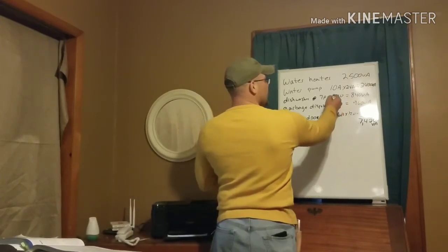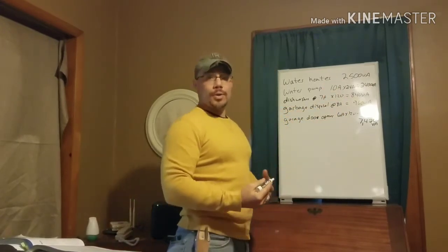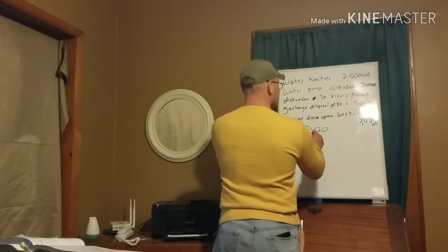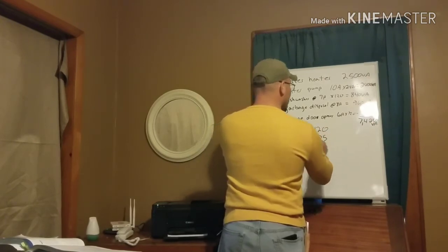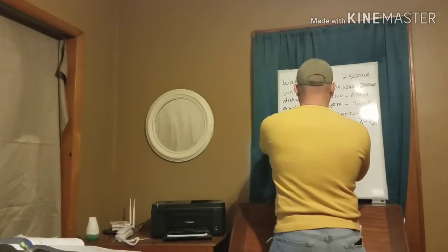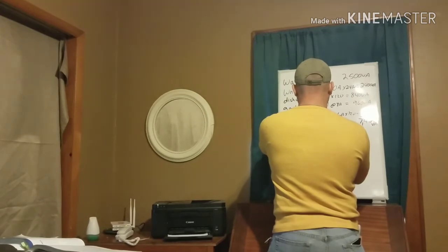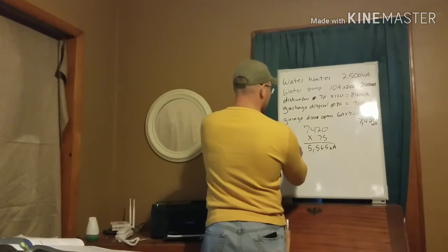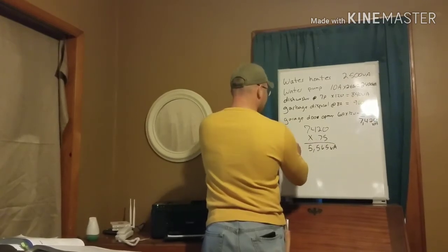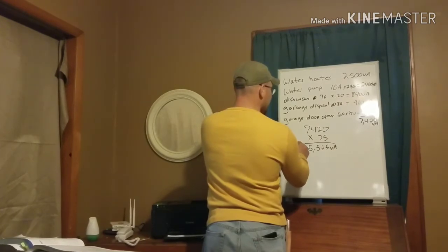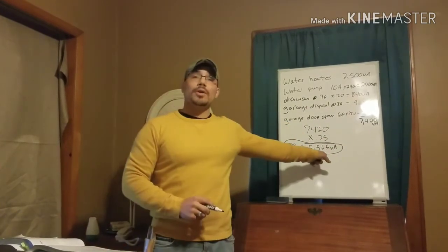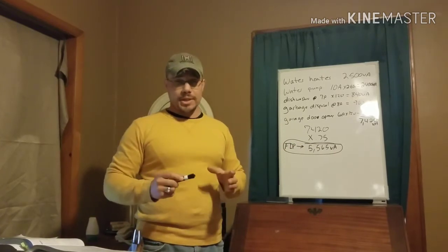That's our total for all fastened-in-place appliances. We have five appliances, so that's four or more, meaning we can apply the 75 percent demand factor. We take 7,420 VA times 0.75 and we get 5,565 VA. That is our fastened-in-place appliance load — the number we would use in our calculations for our ungrounded service conductors.